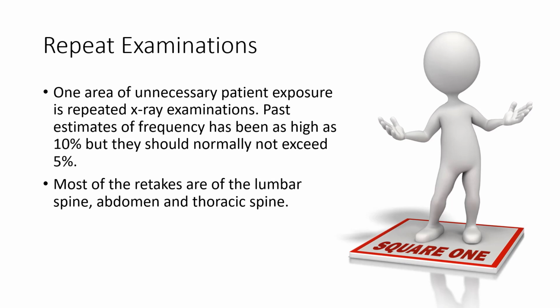When we had film screen, we used to have an average of up to about 5% of exams being repeated, and some hospitals or clinics had a higher rate than that. With automatic exposure control, we really don't see that in digital imaging, but we do have guide numbers that will let us know if the image was done correctly. If it doesn't correspond to the number that it is supposed to, you need to analyze the image and repeat it.